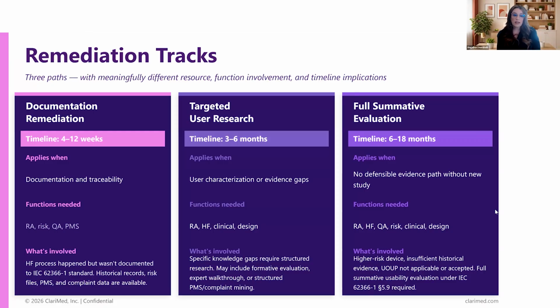So when you look at your documentation and traceability, does this all make sense? Does your GSPR say the same references? Does your IFU call out the right outputs from your design validation, including human factors? Everything is coming together. So it's really pulling it together and making sure the story is there. So no additional testing is required. You just need to work through the documentation.